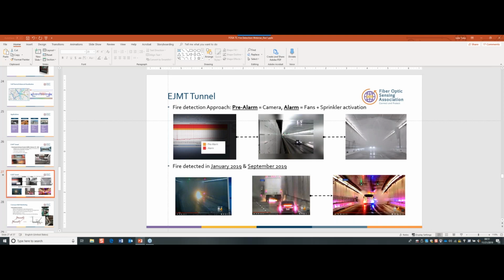The fiber optic linear detection is not worried about dust and everything else. We don't need to purge the system. We are monitoring the temperature, and we can monitor the rate of rise. So aspiration systems are fantastic, but in a very controlled environment. Our system is made for this type of environment. It's very industrialized, and we can monitor the rate of rise and the maximum temperature as fast as or as good as an aspiration system in different applications.